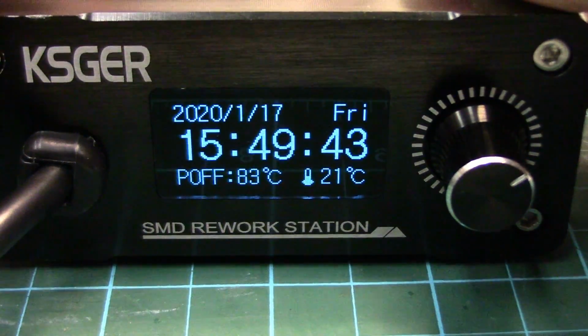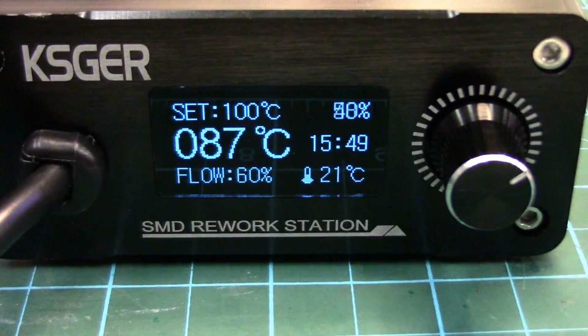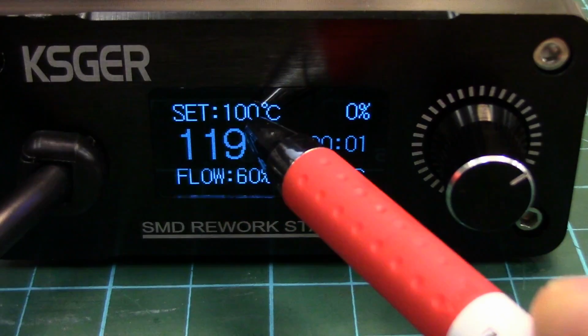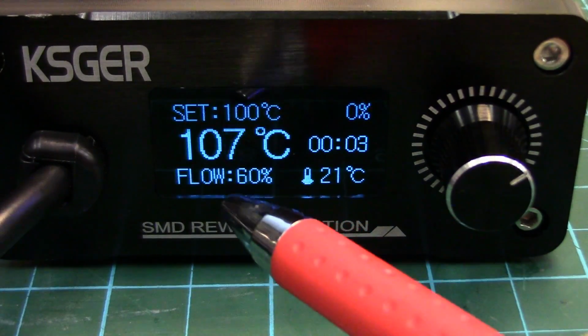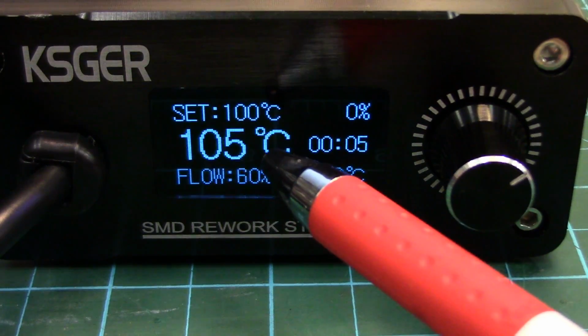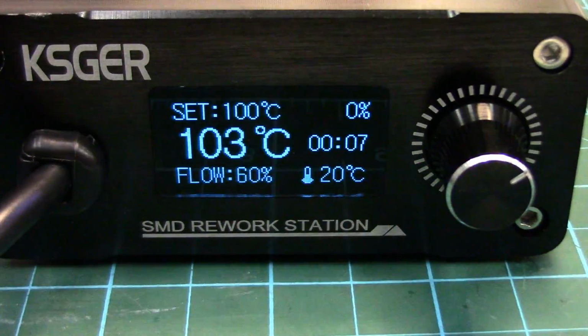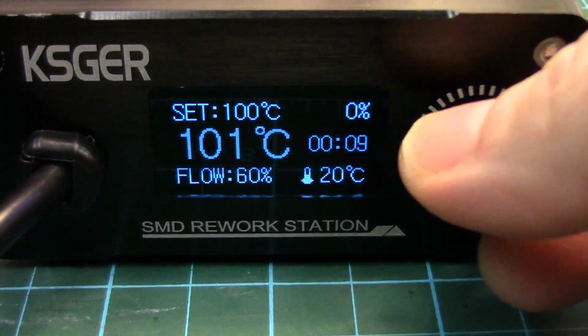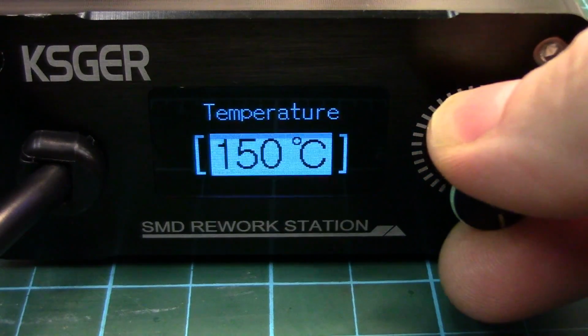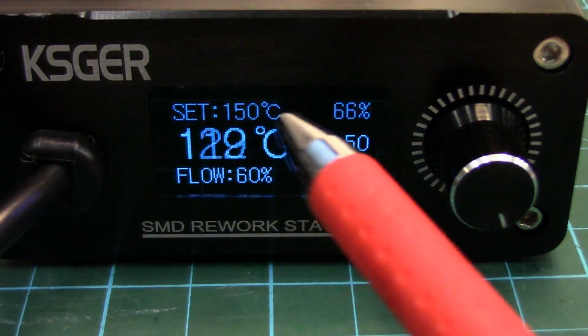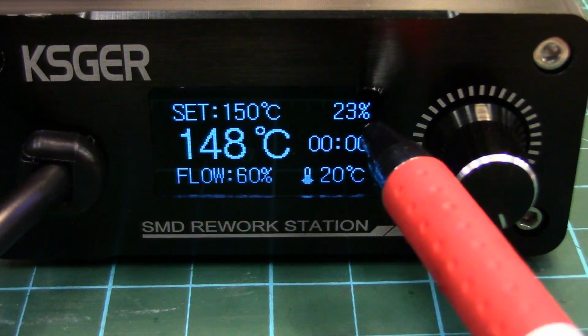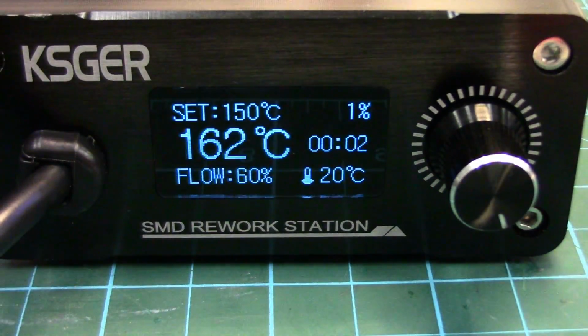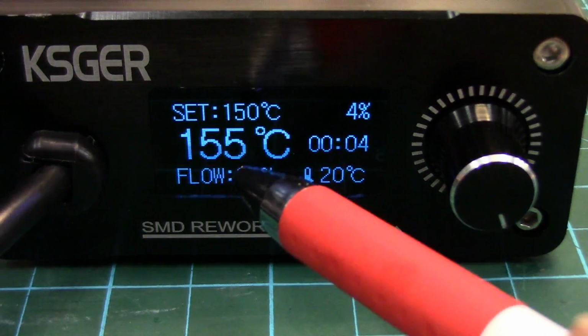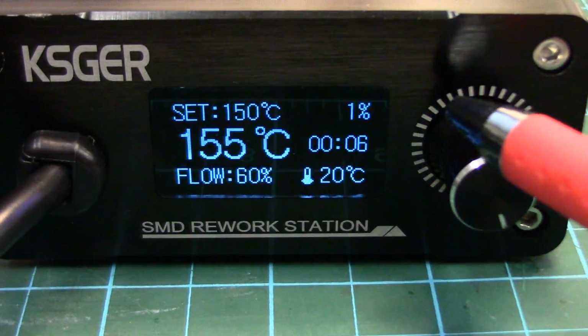Now when we turn it on, okay, it shows the set temperature, 100 Celsius, and the actual temperature that the sensor is reading. And to dial that up, we just turn the dial. Let's go up to 140, or actually 150 Celsius. And you'll see this go up to 100% power output, and then it's dropping down as it comes up to temperature. Now it's just maintaining the temperature.